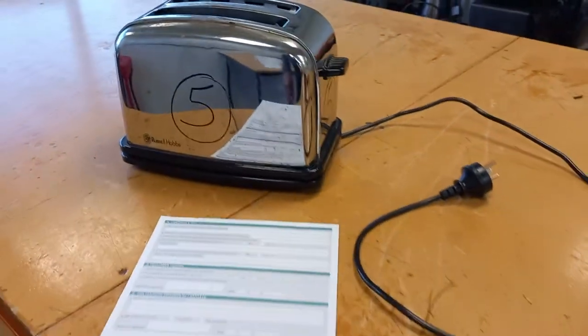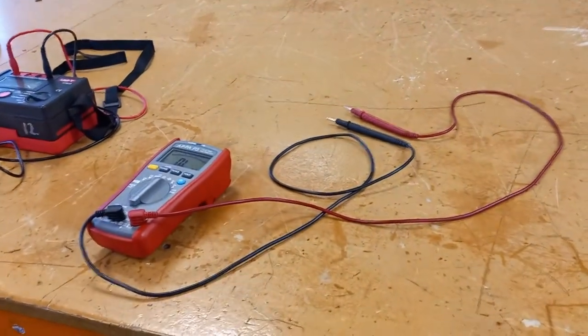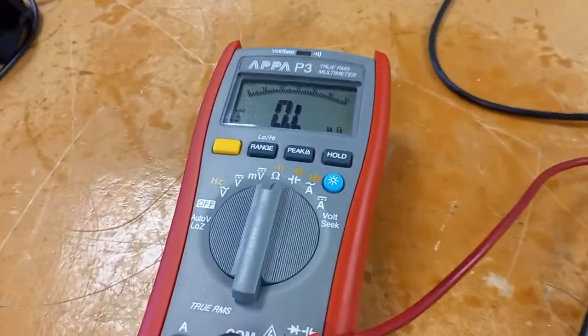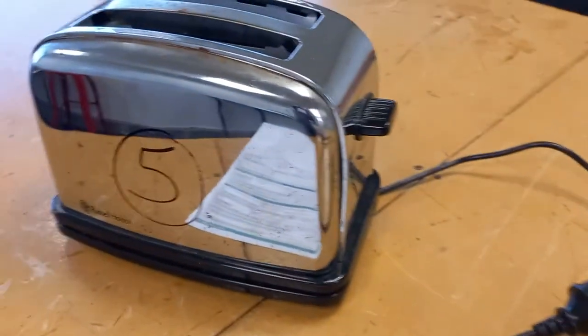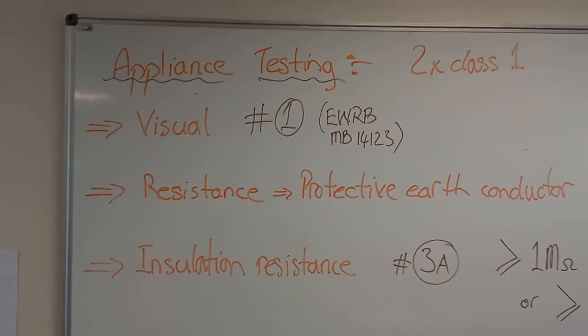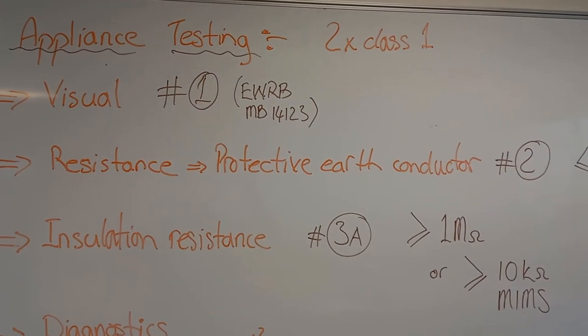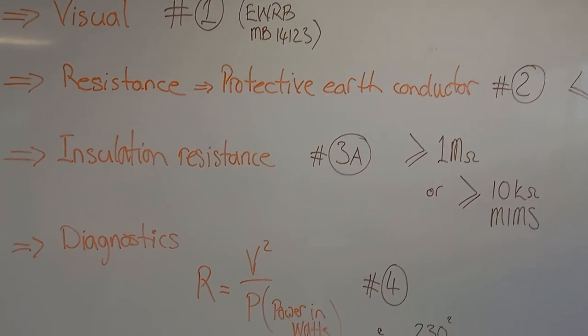There is a quick overview of the basics of testing a Class 1 appliance. You'll need a low ohms reading multimeter, an insulation resistance tester, and your Class 1 appliance. This EWRB test form can be downloaded from the EWRB website. Follow these steps: first the visual, followed by the resistance of the protective earth conductor, then the insulation resistance, and finally the diagnostics. Thank you for watching.